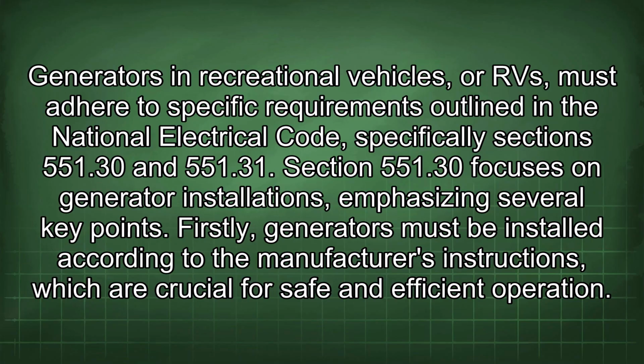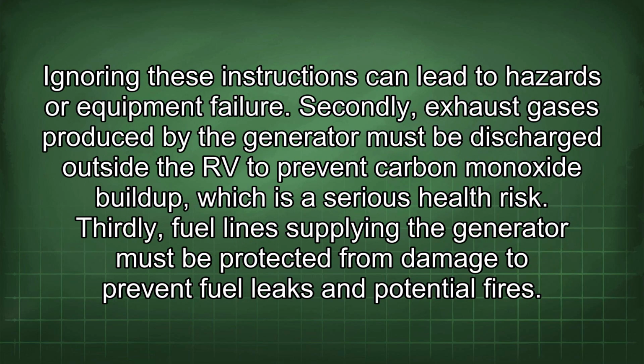Generators in recreational vehicles, or RVs, must adhere to specific requirements outlined in the National Electrical Code, specifically sections 551.30 and 551.31. Section 551.30 focuses on generator installations, emphasizing several key points. Firstly, generators must be installed according to the manufacturer's instructions, which are crucial for safe and efficient operation. Ignoring these instructions can lead to hazards or equipment failure.